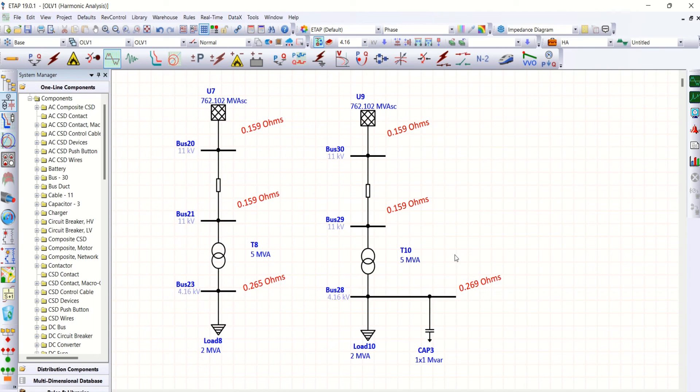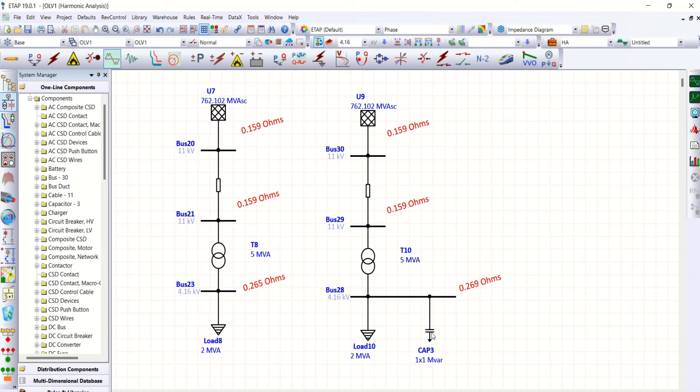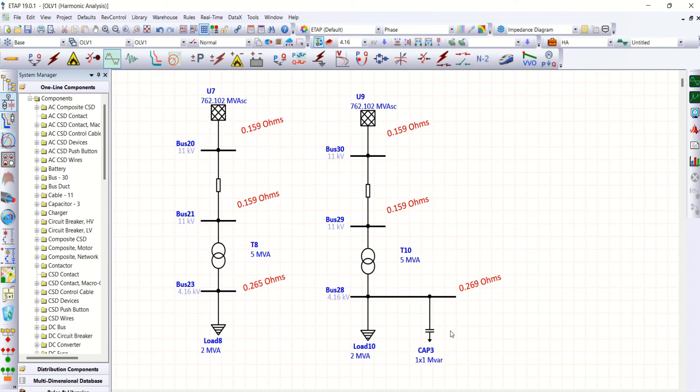With this, I hope you can understand the impact of capacitor bank in the system. This is not only increases power factor of the system, but also increases total harmonic distortion if the load has harmonic spectrum.